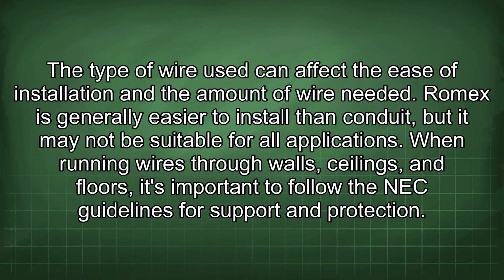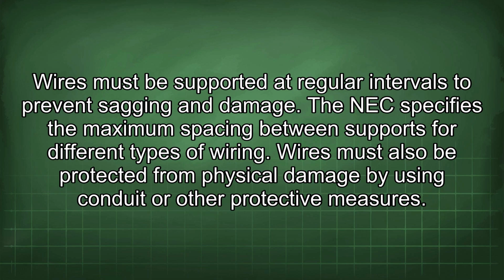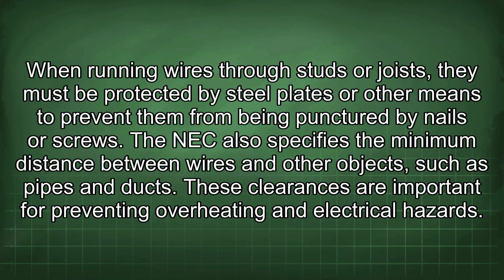When running wires through walls, ceilings, and floors, it's important to follow the NEC guidelines for support and protection. Wires must be supported at regular intervals to prevent sagging and damage. The NEC specifies the maximum spacing between supports for different types of wiring. Wires must also be protected from physical damage by using conduit or other protective measures. When running wires through studs or joists, they must be protected by steel plates or other means to prevent them from being punctured by nails or screws. The NEC also specifies the minimum distance between wires and other objects, such as pipes and ducts. These clearances are important for preventing overheating and electrical hazards.